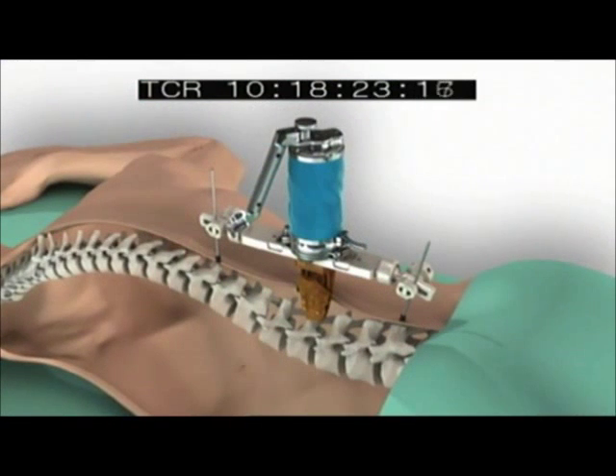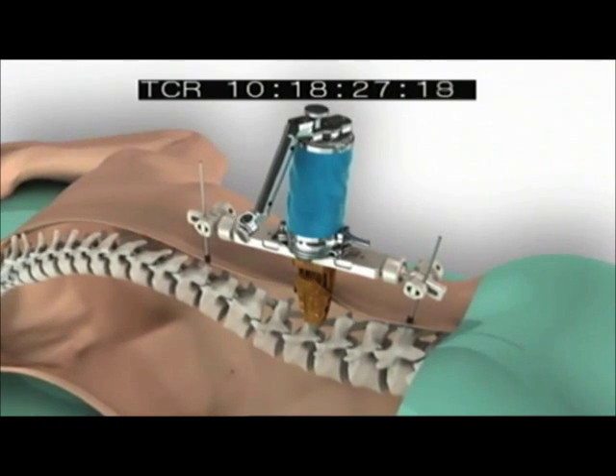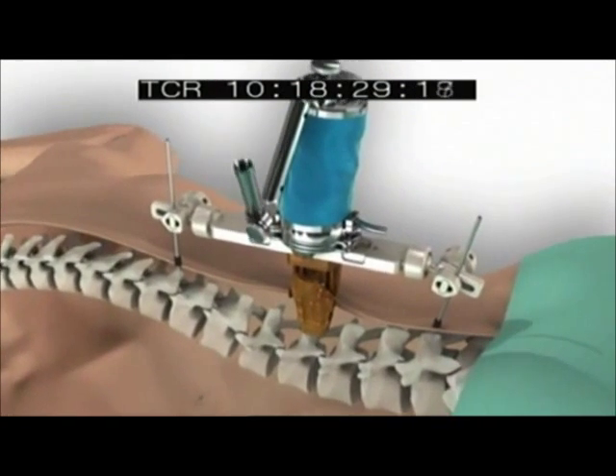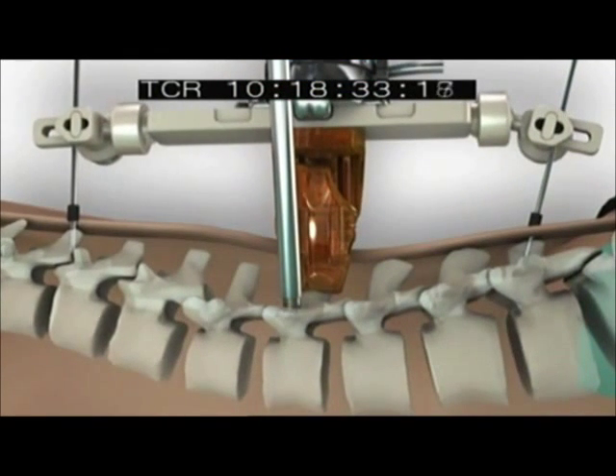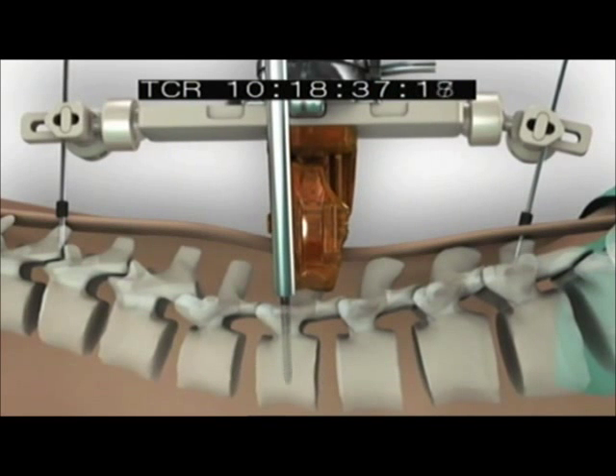The guidance system moves SpineAssist in tandem with doctors during surgical procedures. We place it on a track where the robot can move from station to station. Once it's moved into position, we then insert a small tube or metal tube that goes right through here. We then pass a drill right through that hollow tube. We make sure that it all feels like it should feel and we insert the screw right in that same angle.